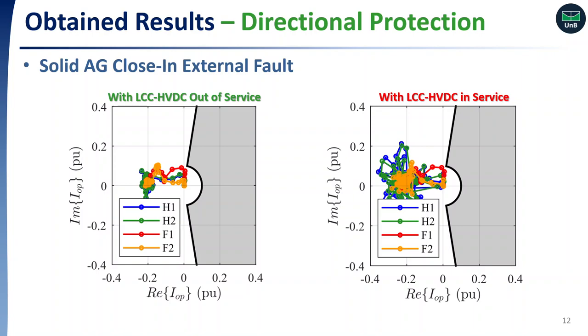Finally, we show results for the directional protection function. Here we depict the response of the zero-sequence directional function of the relay at the remote bus for the same AG close-in external fault. As one can see, regardless of whether the LCC bipoles are in service or out of service, the relay sees a reverse fault, as expected. Thereby, a false trip issue is avoided when the directional elements are combined with teleprotection schemes such as POTT and DCB. However, in the case of negative-sequence directional elements, it is recommended not to use small pickup values to ensure security for external faults.